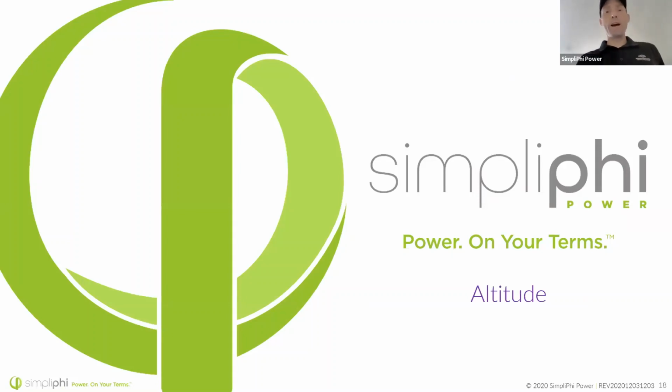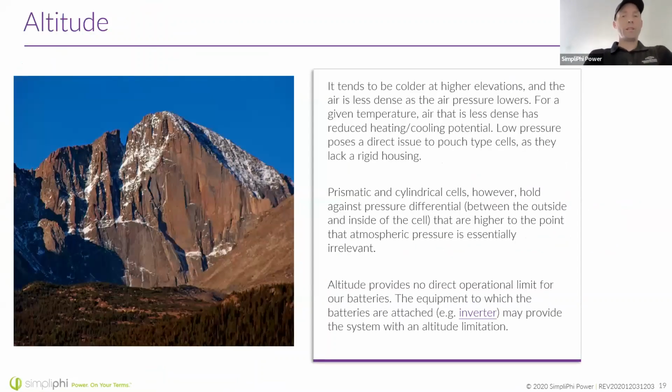Altitude. Our batteries are made on cylindrical cells, and these cylindrical cells are hermetically sealed, so they can go to high altitude, low pressure. Low pressure can cause problems for prismatic and particularly for pouch cells, but it does not cause a problem for cylindrical cells. So our batteries, which are based on cylindrical cell manufacture, have no problem going to high altitudes. However, it's important to note that low temperatures are typically associated with high altitude locations, so it's important to pay attention to the temperature at high altitude, because you can have a low temperature environment.